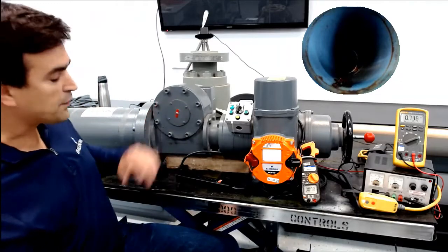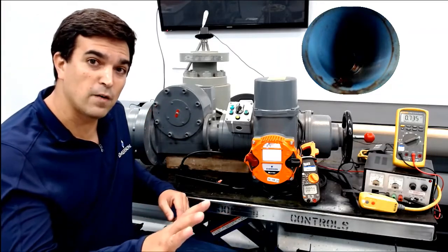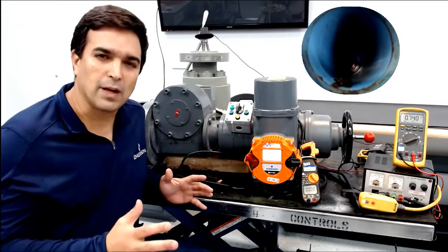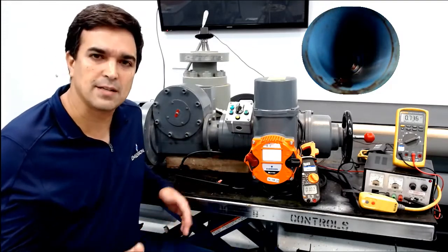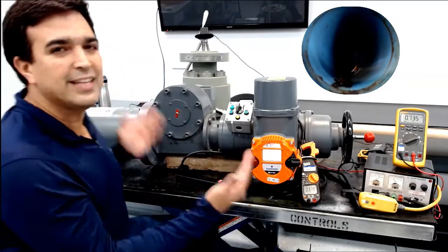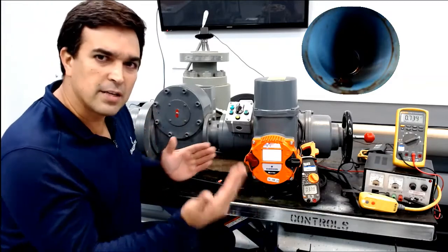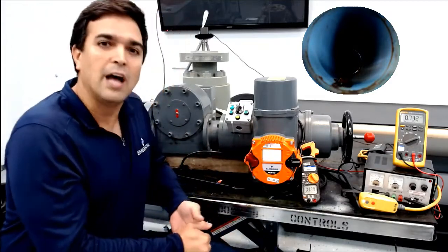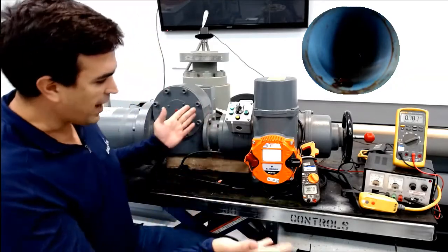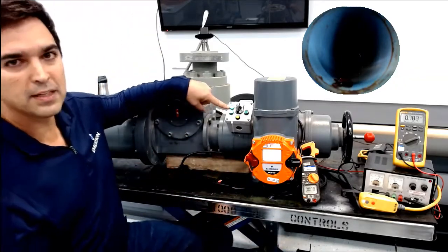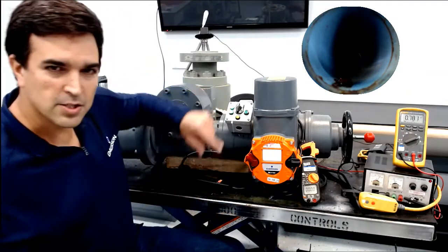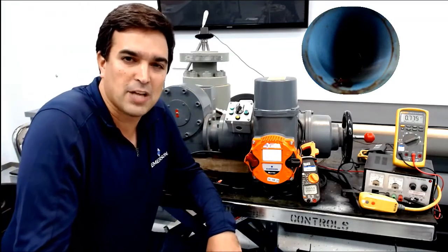It's going to run the motor up to 70%, remain there 5 seconds, and then bring it back. Again, what is important here is that if you have this system in a SIS application, it's critical. But if not, what it's telling you is that you can test your system and be sure that it's doing what you need it to do at the right time, and it's going to be a reliable solution. So finally, you see we have a thumbs up, it gives you the light on, which means that the partial stroke was okay.